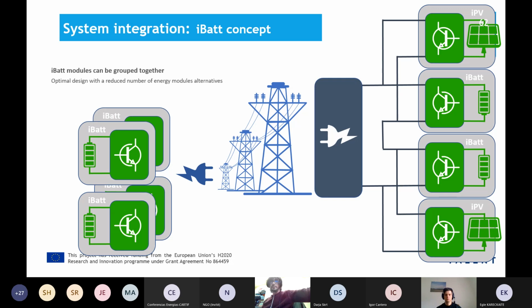The solution, because of the control system, offers flexibility regarding independent operation of the energy modules. For example, it allows something impossible with series connection: different modules can be operated at the same time, even charging and discharging, or the power each module gives to or absorbs from the grid could be different, completely asymmetrical.